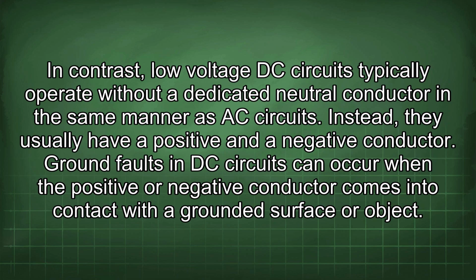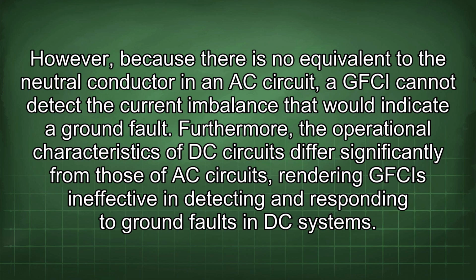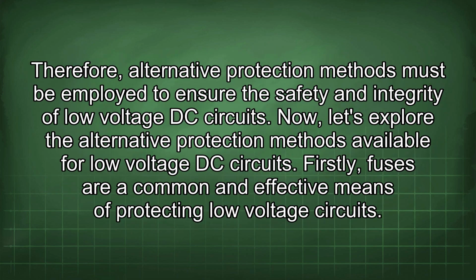In contrast, low-voltage DC circuits typically operate without a dedicated neutral conductor in the same manner as AC circuits. Instead, they usually have a positive and a negative conductor. Ground faults in DC circuits can occur when the positive or negative conductor comes into contact with a grounded surface or object. However, because there is no equivalent to the neutral conductor in an AC circuit, a GFCI cannot detect the current imbalance that would indicate a ground fault. Furthermore, the operational characteristics of DC circuits differ significantly from those of AC circuits, rendering GFCIs ineffective in detecting and responding to ground faults in DC systems. Therefore, alternative protection methods must be employed to ensure the safety and integrity of low-voltage DC circuits.